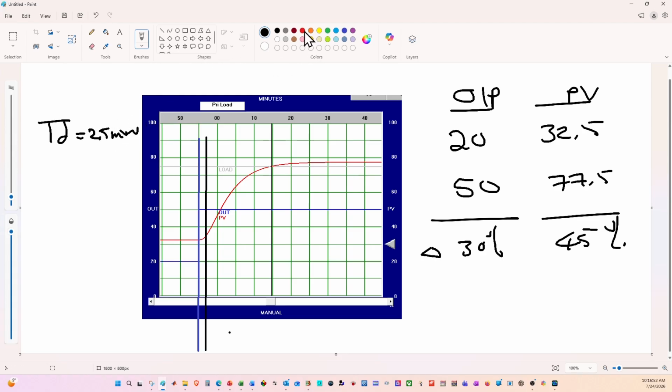I'm going to change across to a red pen. The time constant is the time that elapses from when the process variable started to change until it gets to about 2/3 of the way. In other words, that's the dead time we can see between those 2 points. So the time constant is probably going to be 5 minutes plus 2 plus 3. Maybe 5, 6, 7, 8, 9, 10. Maybe it's going to have a value of about 10 minutes. Okay, totally up to you. Near enough is good enough. Very thumbs up value. It looks like we're going to work with those values.